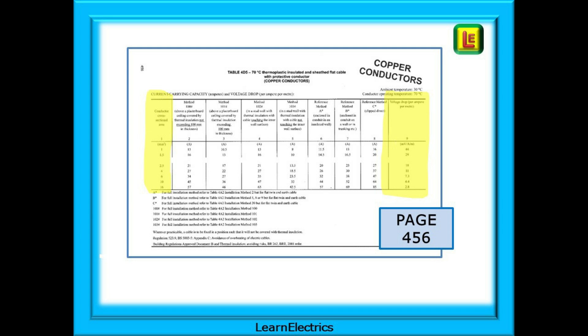And here we are at table 4D5. With practice you will learn to find it easily. In this video we have taken the long route so that you understand what is going on. After a short while you will just remember that table 4D5 is on page 456 and go there without a second thought. You can see the conductor sizes highlighted on the left and the voltage drop factors to use in the formula are highlighted on the right. One millimetre cable uses a factor of 44 in the formula and four millimetres twin and earth uses a factor of 11. The bigger the cable the smaller the volts drop as it's easier for electricity to flow through bigger conductors.